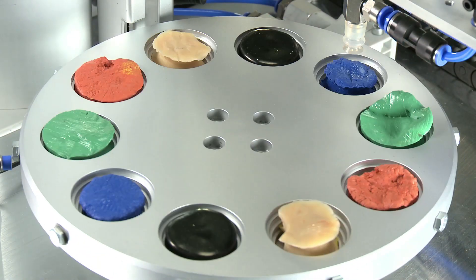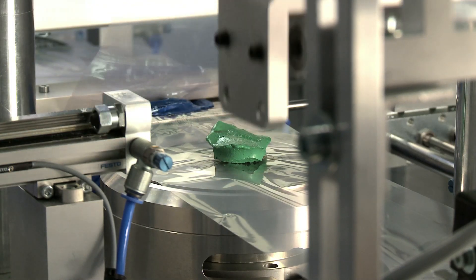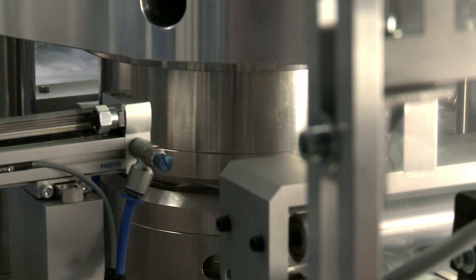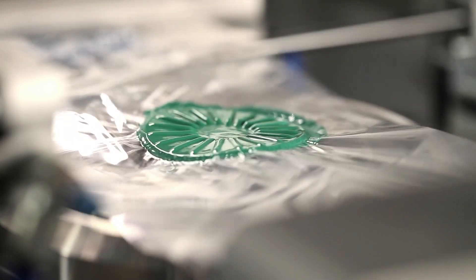This performance is complemented by an optional carousel-based auto sampler, allowing increased productivity through unattended testing of rubber samples. A pneumatic transfer system and film advancing mechanism provide automatic sample feed that is reliable and tolerant to non-ideal sample shapes.